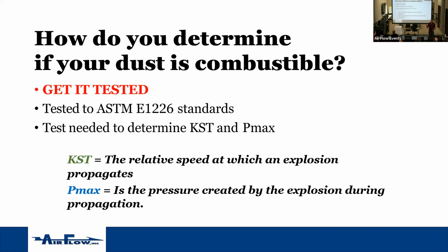And they'll actually test it for you, and you'll get two numbers back, the two most important numbers that you can get. The KST, which is the speed at which that explosion will propagate. So how fast that explosion leaves that collector and goes into or backwards through your dirty duct, leaves and goes through your discharge into your collection drum, or it goes through your collector down to your cleaner side, whether that's returning to your building or outside. And the Pmax is the pressure that's created during it. So how big is the pressure of that explosion? So you've got KST as the speed, Pmax is the pressure, how big it is. So you have to get it tested. That's the big thing that has to happen.